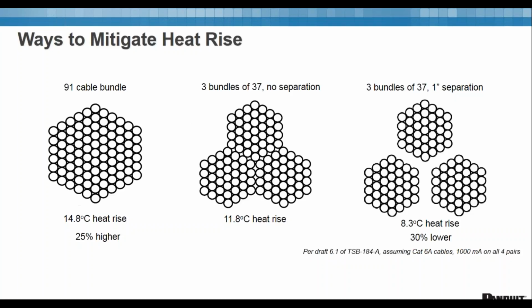A common question that gets asked a lot here is, what is a bundle? A bundle refers to tightly packed cables. I can't really give a better definition than that. At TIA, I'm sure we could spend all day debating the definition, but it's really a group of tightly bundled cables. And that's significant because these are bundles of cables where you can imagine some sort of cable tie or hand tie wrapped around it, keeping them together. But then you've also got cable trays where you're starting to throw cables on top of each other and just lumping them together. That also can count, provided they're tightly packed.